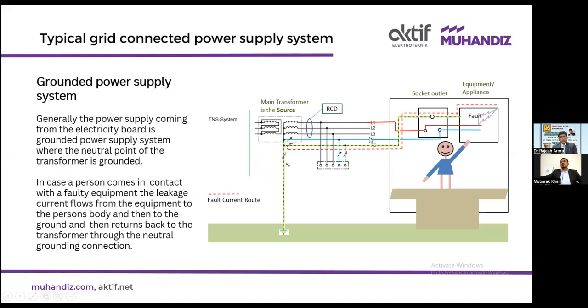L1 and neutral will go to, for example, A wing. L2 and neutral will go to B wing. L3 and neutral will go to C wing. Consider you live in A wing, so here it is L1 and neutral. L1 will get connected to the phase point of the socket, neutral will come to the neutral point of the socket, and the earth connection will be connected to the earthing point. If you plug in an equipment, it will get connected here. I have made a very simple block diagram just to explain without much complication. So this is the equipment.